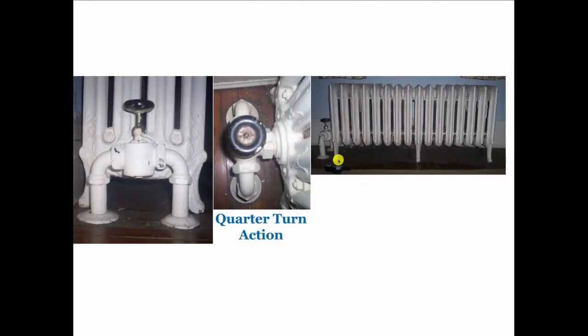This picture was posted on our website by a homeowner who just bought this house and wanted to know what the heck this thing was. There's the Honeywell unique valve, and notice here the air vent is way out on the end. The guy told us that with that little baffle only going in just past the first section, when he gives it a quarter turn the radiator very quickly heats. Gravity hot water heat will move very quickly through a radiator if the piping is all right. If you ever see something you don't know, just take a picture like this guy did, bring it to heatinghelp.com, post it on the wall, and somebody will answer you within minutes and tell you exactly what you're looking at — the site probably also has the literature for that product.